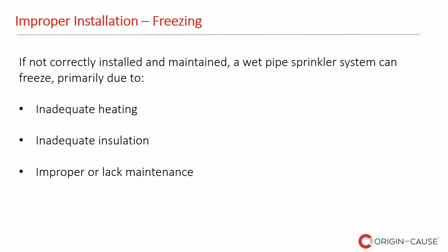So again, when it comes to freezing, we have to look not only at the installation, not only at the maintenance, but also whether there was appropriate heating provided to that system. So if a wet system is adequately installed, properly maintained, but it still freezes, it can all lead to some issue with the heat in the building. So sometimes we tend to jump to conclusions, say, oh, it froze, must have been improperly maintained or improperly installed. But let's not forget that in some cases, the heat to the building is not necessarily a guarantee.